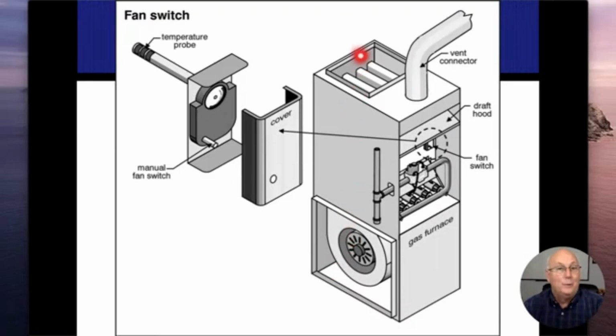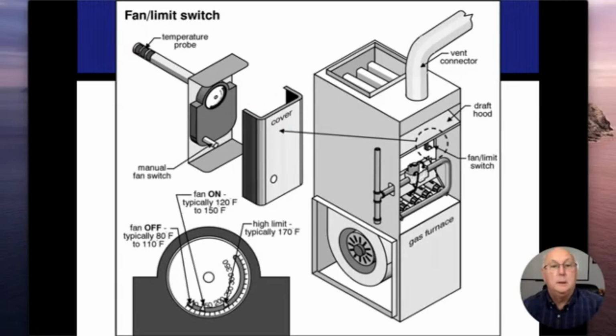All right. So if that blower fan fails, whether the motor seizes up, comes loose, something blocks it, the wires come disconnected, whatever, I'm not able to remove the BTUs. So this furnace is going to get hotter and hotter and hotter. That's what this high limit switch or fan switch does. All right. Older units, this was a dial type machine on here, and it would have that same coil that we saw with the thermostats on there. And this is actually what turned the fan on and off back in the day.